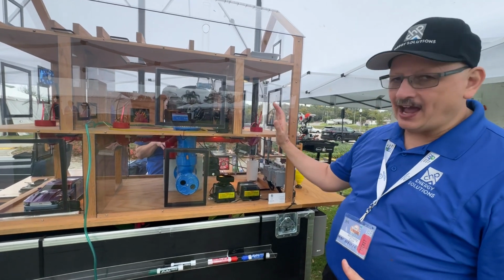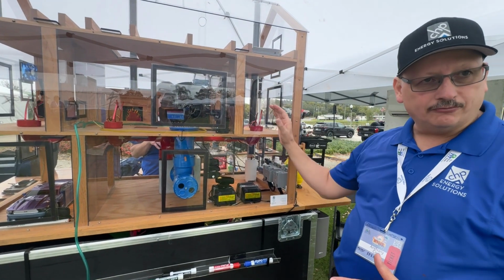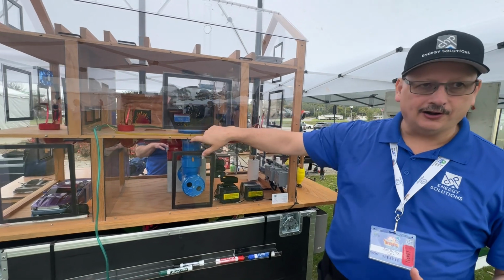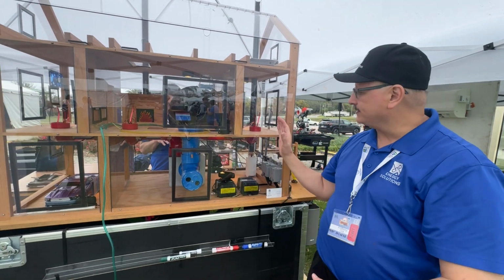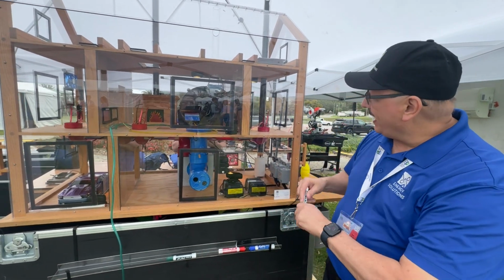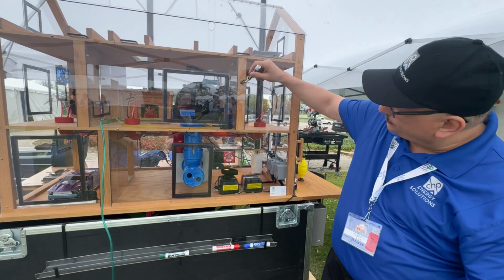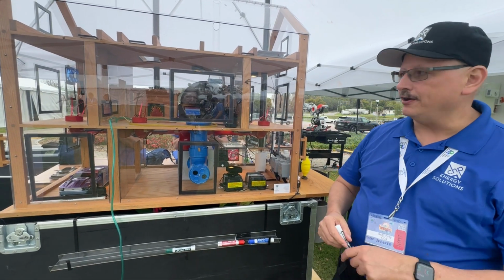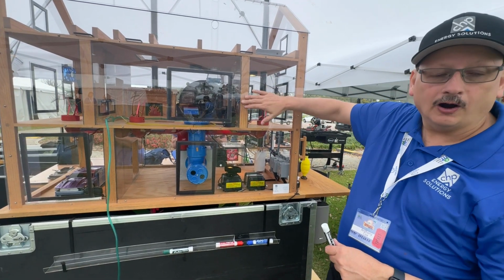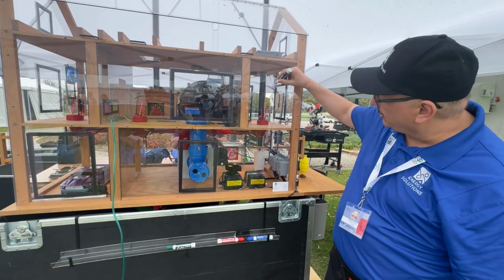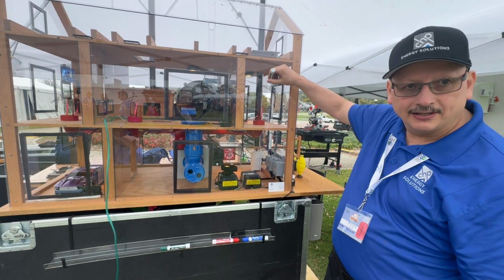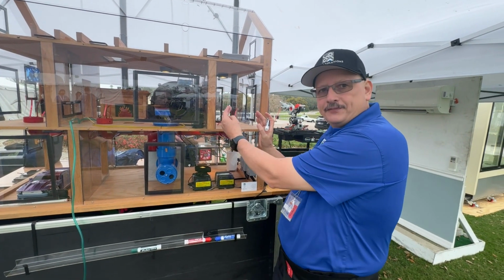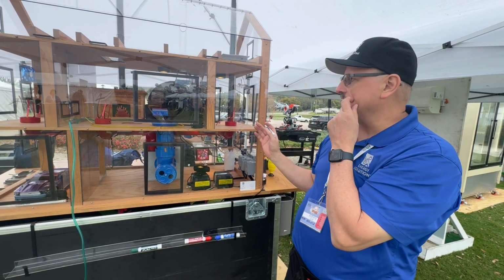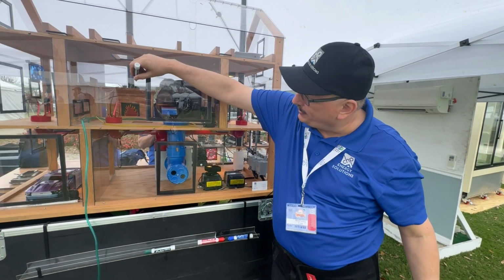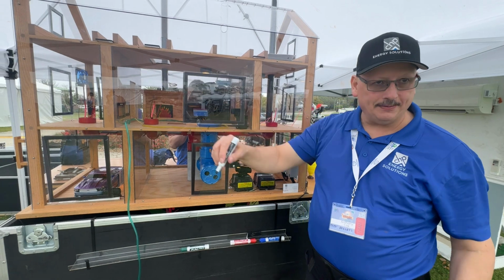Basically, the air's behind in the room, and if you only have returns in the middle of the house, the air has to go from that room, and if the door's open, it can go through the door over to that return. But if the door's closed, especially for long periods of time, this room gets pressurized. You're basically cutting off the supply air's path back to the return. So if this room gets pressurized, you can guess what's going to happen over here—it may get depressurized.